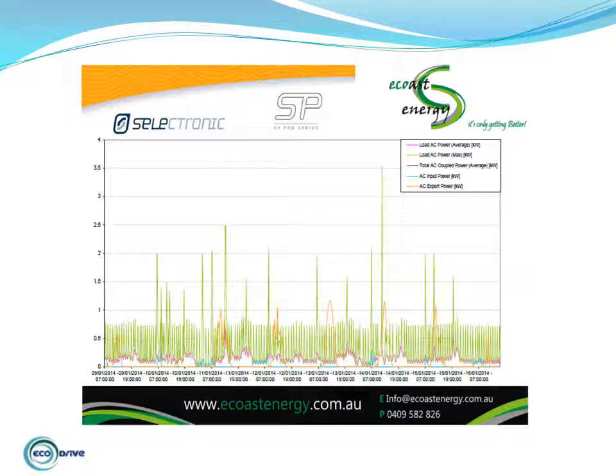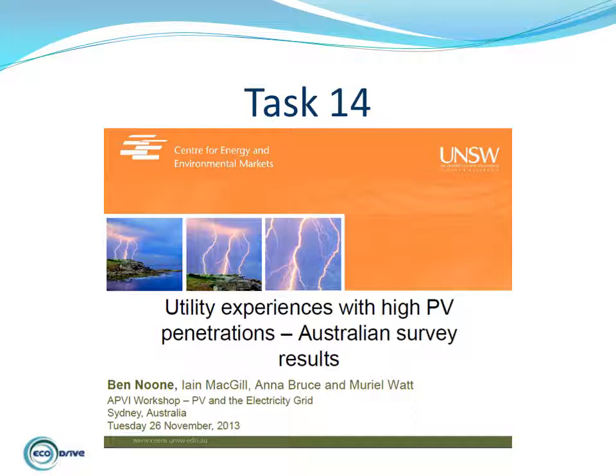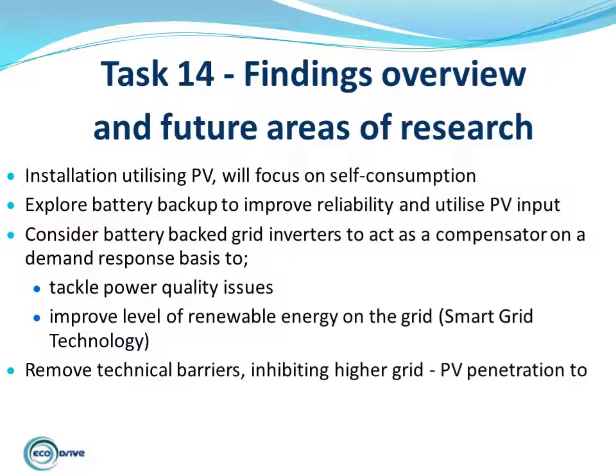Limits of PV penetration are currently being studied by an international energy agency involving 13 countries, and a seminar titled Task 14 was held at the University of New South Wales in November of 2013. The aim of the seminar is to navigate a way into the future with greater PV input and overcoming limitations. Some of the findings and future areas of research from that seminar were: installations utilising PV will become economically focused on self-consumption; battery backup be explored to improve reliability and to better utilise PV input; battery-backed grid inverters be considered to act as compensators on a demand response basis to tackle power quality issues and to improve the level of renewable energy on the grid; and smart grid technology to remove the technical barriers that inhibit high penetration of PV onto the grid.